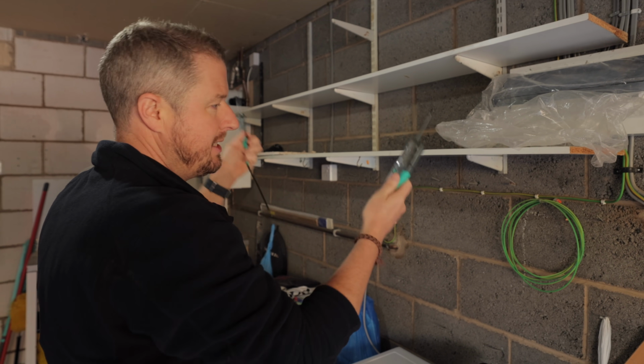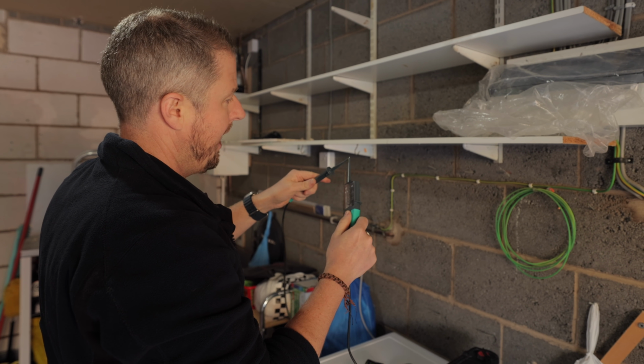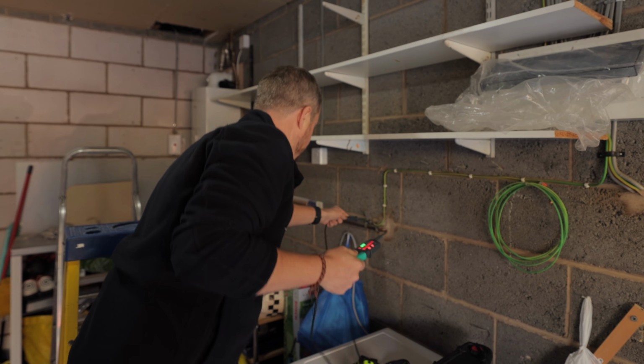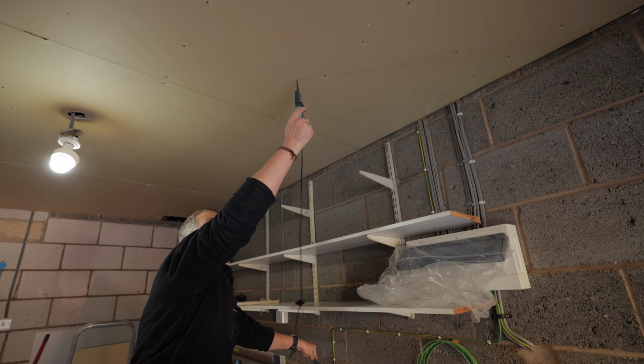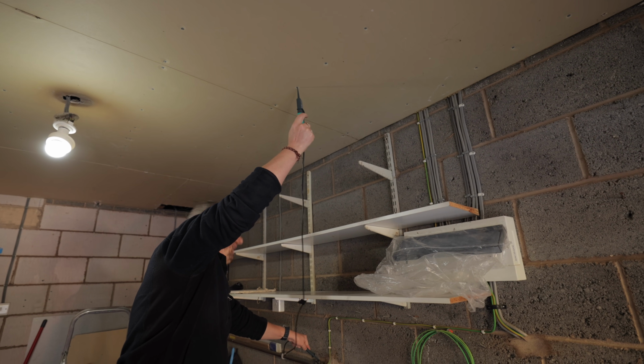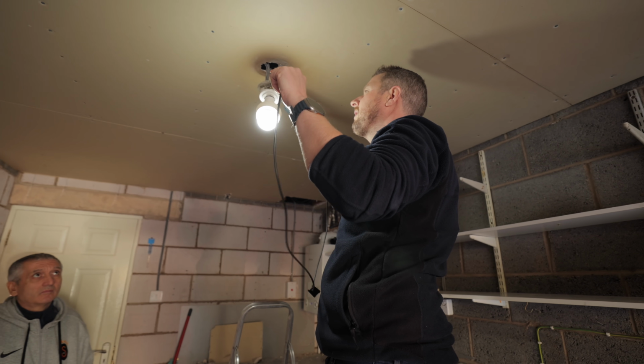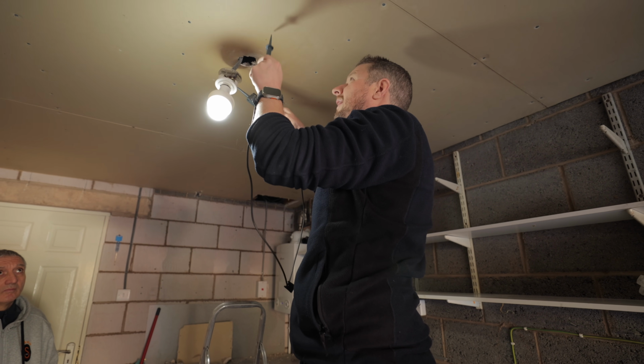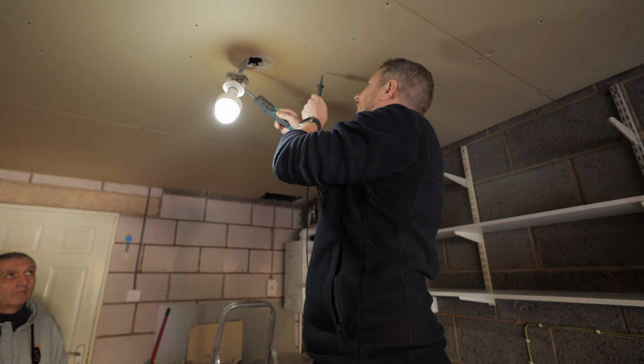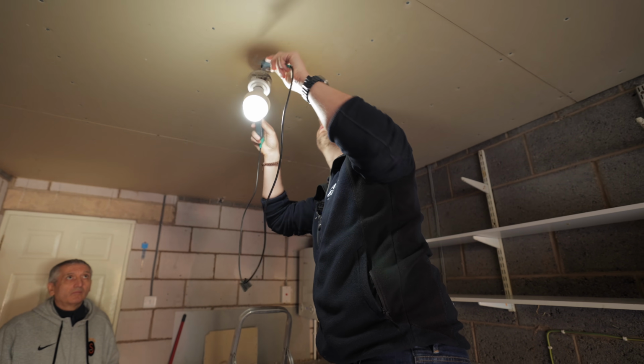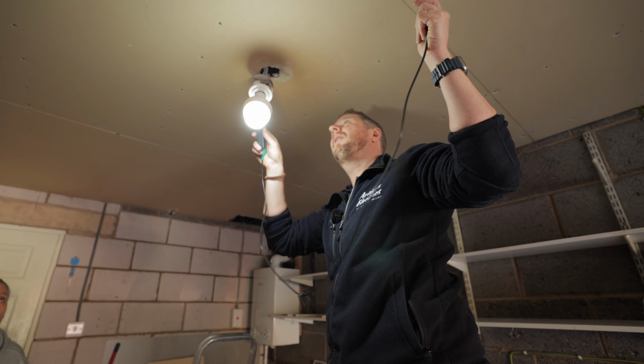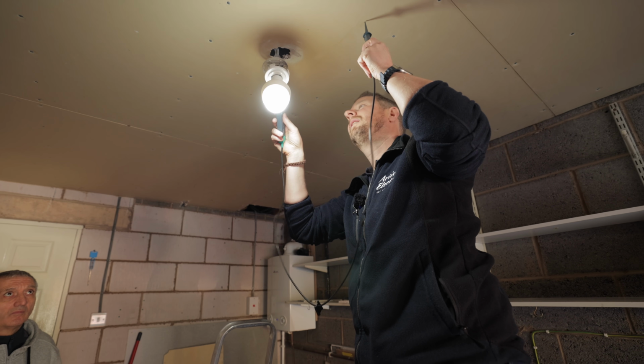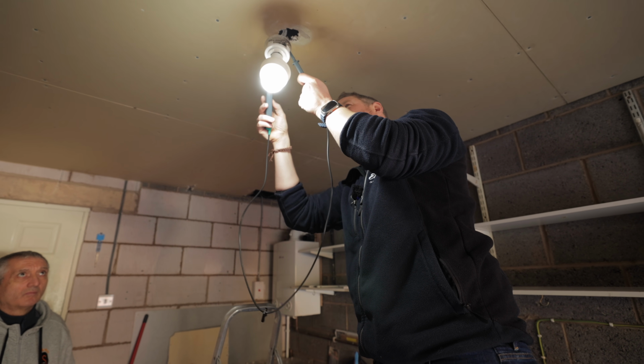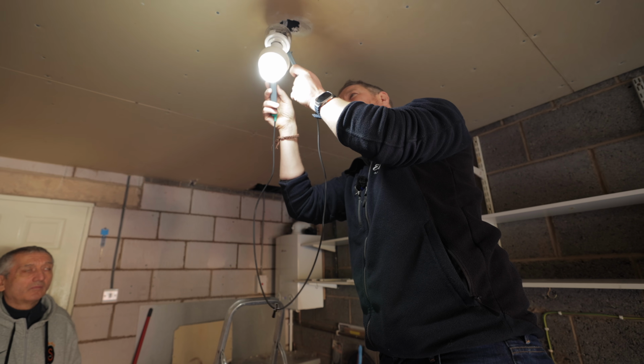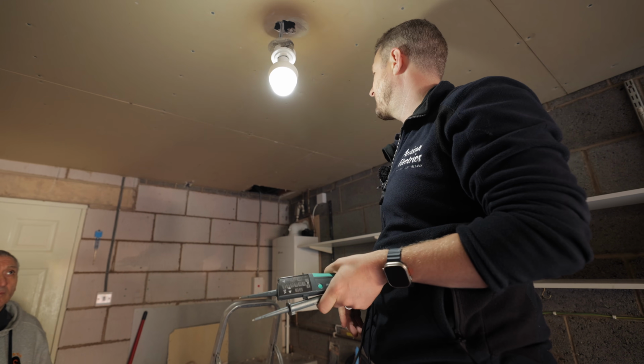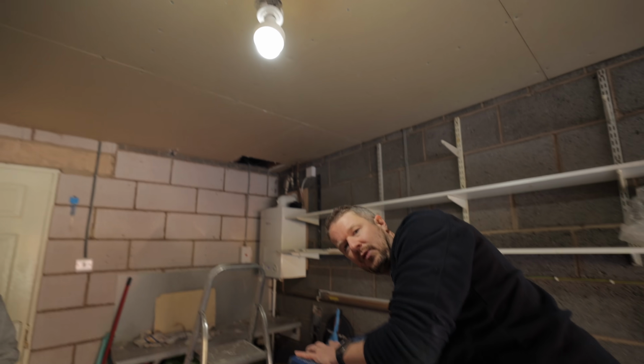So what I'm going to do is use a proper voltage indicator here, and test from the earth to the ceiling and see if we've got any voltage. And actually we don't. Let's test here with the earth on the lighting circuit and then the plasterboard. And again, nothing. Let's check on the neutral. Okay, still nothing. Let's check on the live. So it doesn't seem like there's any kind of high voltage here on the ceiling, but there's obviously enough to trigger the voltage detector. So what we're going to do is an insulation resistance test.